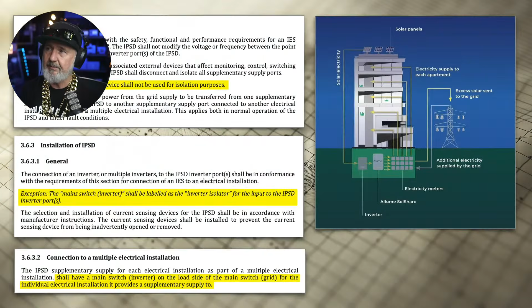And for instance, oops, I've got to get my face out the way. You cannot use semiconductor devices as the means of isolating the supplementary supplies. So they need to be able to have an actual switch as well. So there may well be solid state switching, but when you need to isolate your supplementary supplies at the IPSD, they need to be done with air gap isolation.